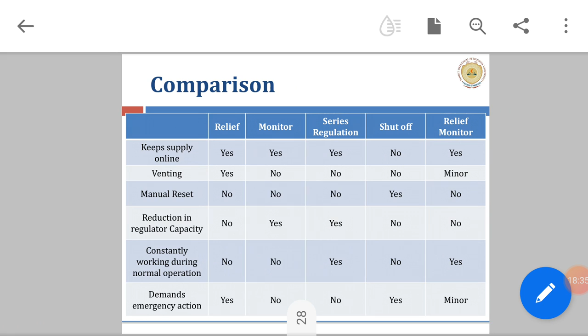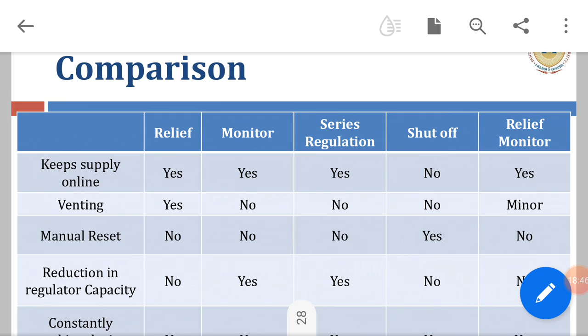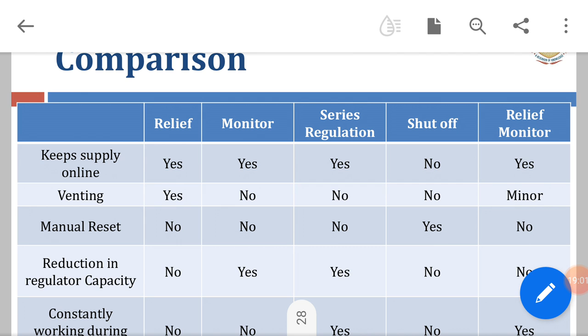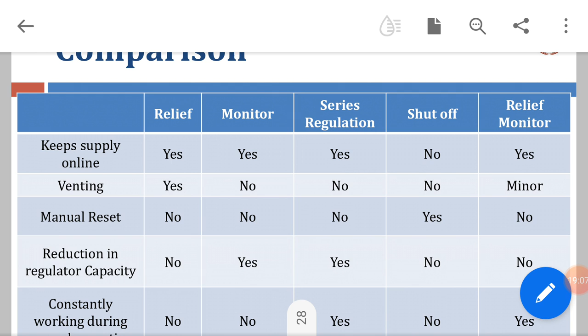Now, if you do a comparison on a couple of parameters on the relief monitor, series regulator, shut-off and relief monitor, then we can see that to keep supply online, for the relief it is yes. For the monitor also yes, for the series regulator yes, for shut-off no, and for the relief monitor it is yes. For venting, for relief it is yes, for monitor it is no, for the series regulator it is no, for shut-off it is no, and for relief monitor it is minor. Manual reset: no for the first three and yes for shut-off.